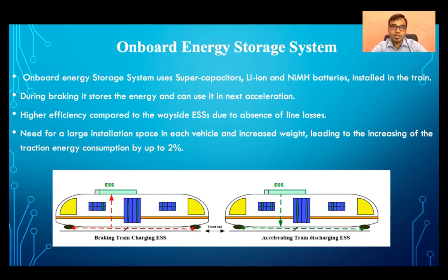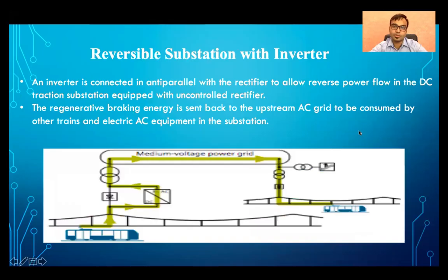Let's discuss another way of utilizing the regenerative energy, called the reversible substation with inverter. In this case, an inverter is connected in anti-parallel with the rectifier to allow reverse power flow from the DC traction substation, which is equipped with an uncontrolled rectifier.